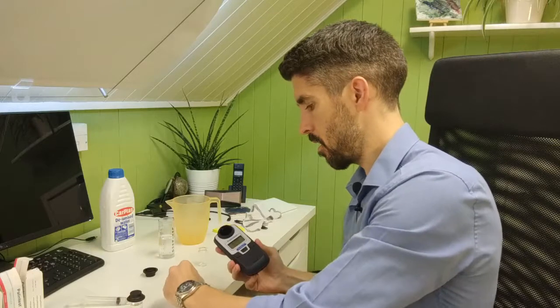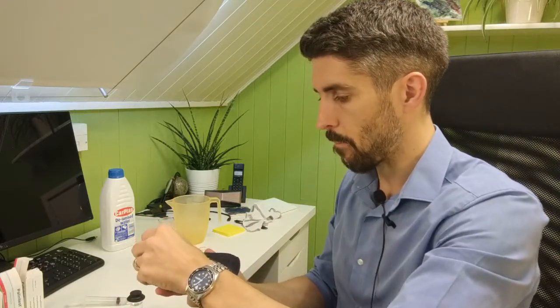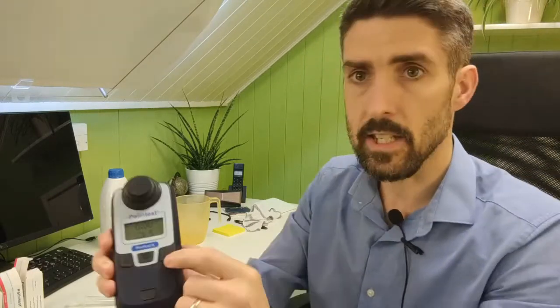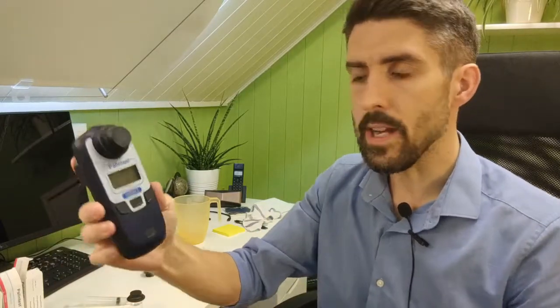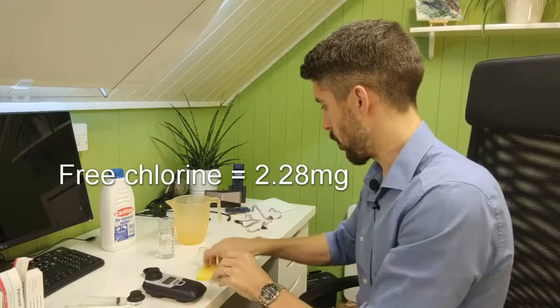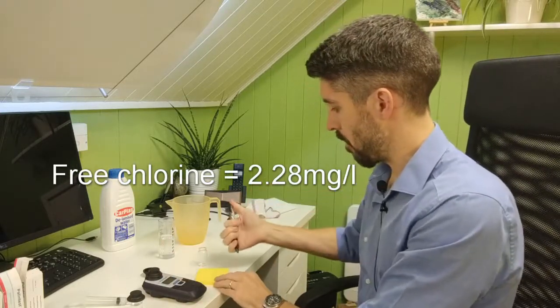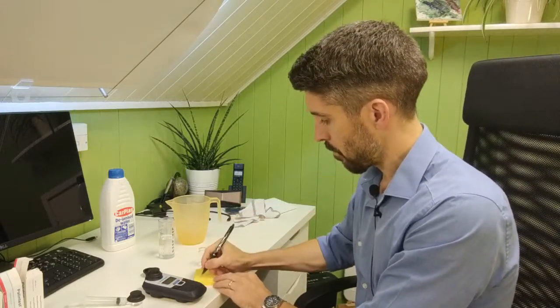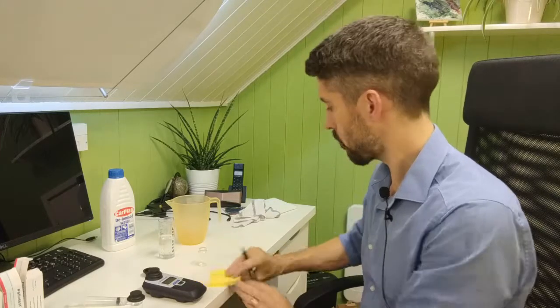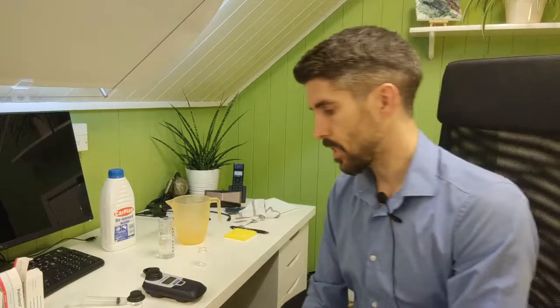Swap the blank for the actual sample that you're going to be testing, and then don't press the blank again, press the test button this time, and then it comes up with 2.28 milligrams per liter of free chlorine. So I'm just going to make a note of that, 2.28. Okay, so that's the free chlorine test done.